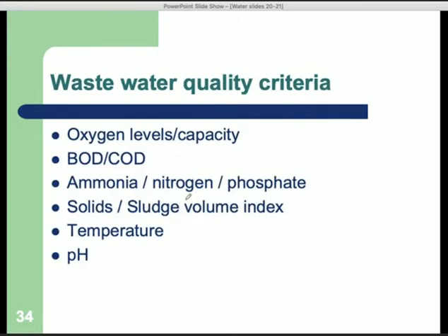Because for wastewater, it's much different. Like I said already, in wastewater, you have to worry about things like ammonia, nitrogen, phosphate. So these things are nutrients that you want to retain. They are clearly on a molecular basis, so none of this stuff will be retained in a sand filter. You have, generally speaking, BOD, and I have a slide about this afterwards. So BOD is biochemical oxygen demand, which really just expresses how much organic waste there is in the water, how much energy there is in the water that we don't need to release.